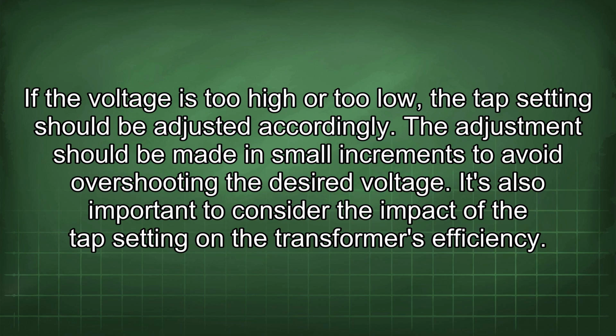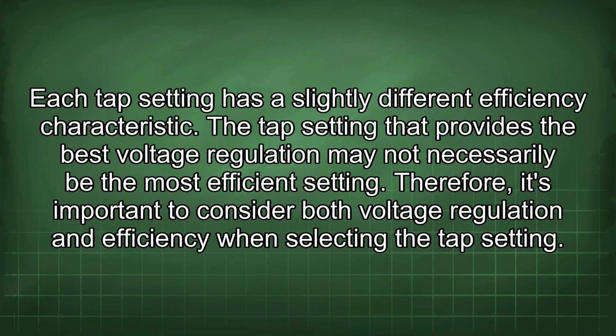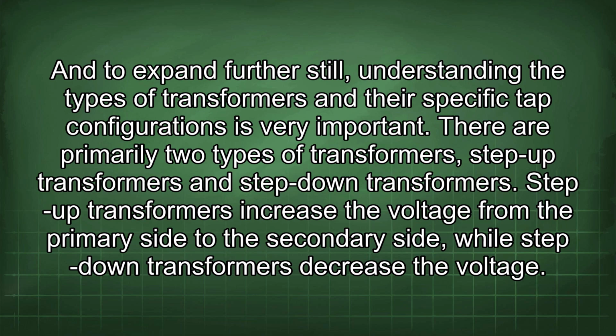It's also important to consider the impact of the tap setting on the transformer's efficiency. Each tap setting has a slightly different efficiency characteristic. The tap setting that provides the best voltage regulation may not necessarily be the most efficient setting. Therefore, it's important to consider both voltage regulation and efficiency when selecting the tap setting. And to expand further still, understanding the types of transformers and their specific tap configurations is very important.